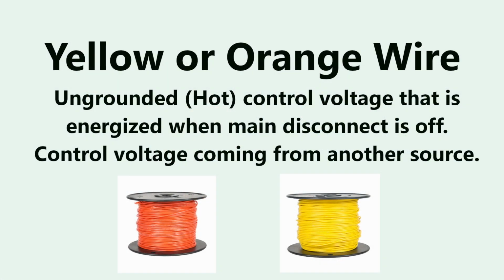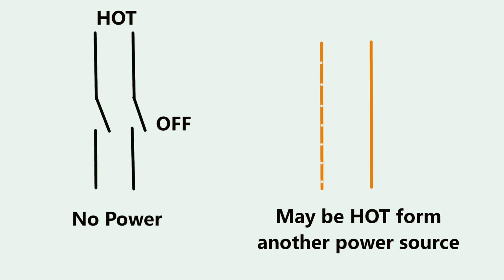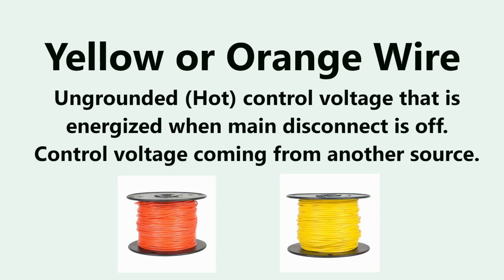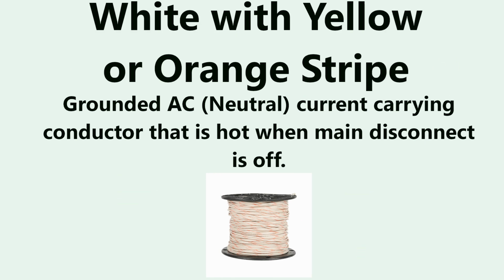If you see yellow or orange wire in a panel, beware. That signifies typically that voltage is coming from another power source outside of that panel. So if you turn the main disconnect off, or the main power off going into that panel, a yellow or an orange wire may possibly still have voltage on it coming from a different source. So always check those with a voltmeter. The other side of that is white with a yellow stripe or white with an orange stripe, and that is going to be the neutral of that extraneous voltage that is coming from another panel.